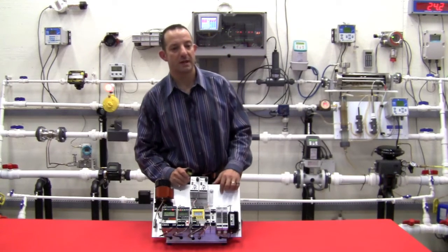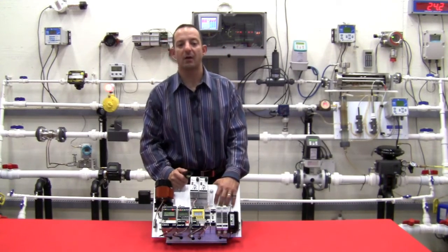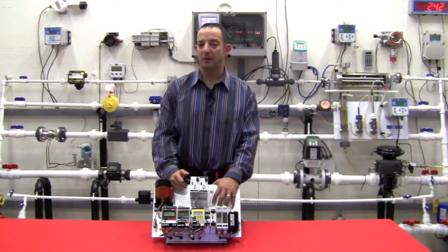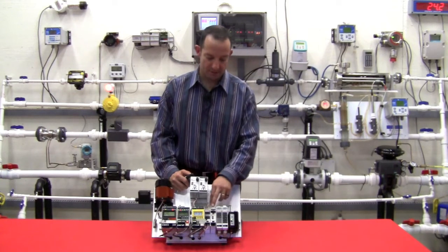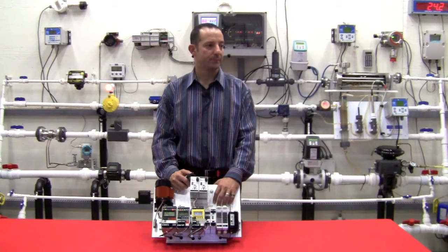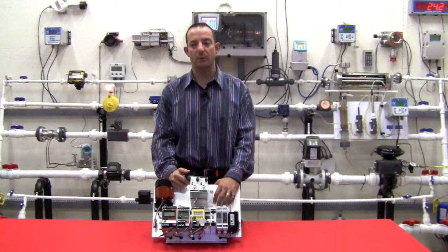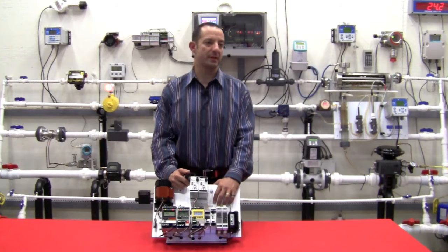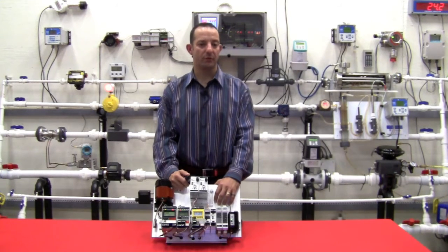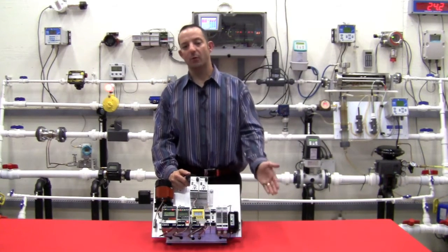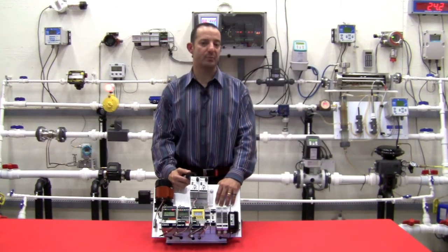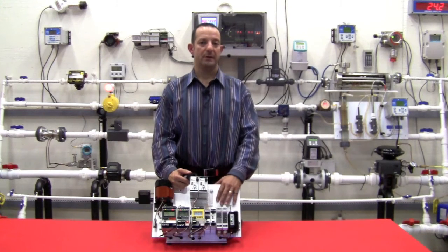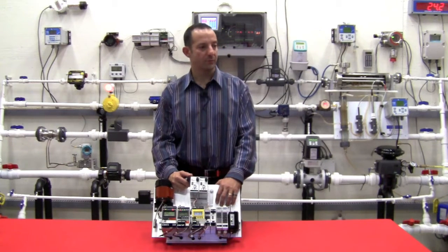The second reason is that PLC and DCS analog input cards are often much more expensive on a per-channel basis than temperature transmitters, particularly when you have mixed temperature sensor types, mixtures of different types of thermocouples or thermocouples and RTDs. You convert them all over to 4 to 20. That's the highest volume, least expensive inputs available on most control systems.